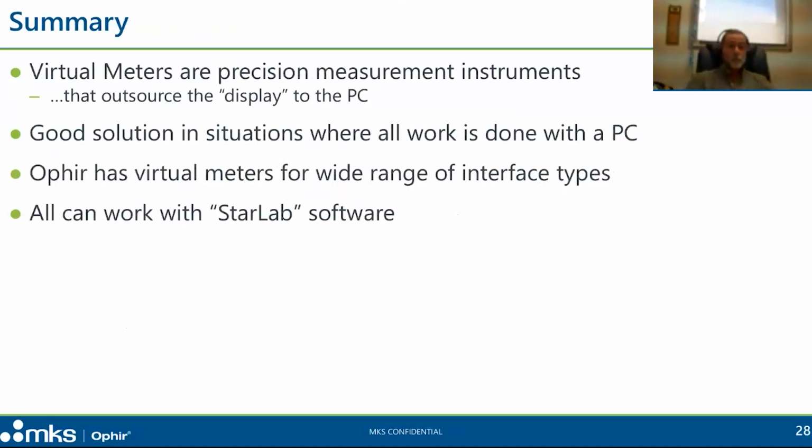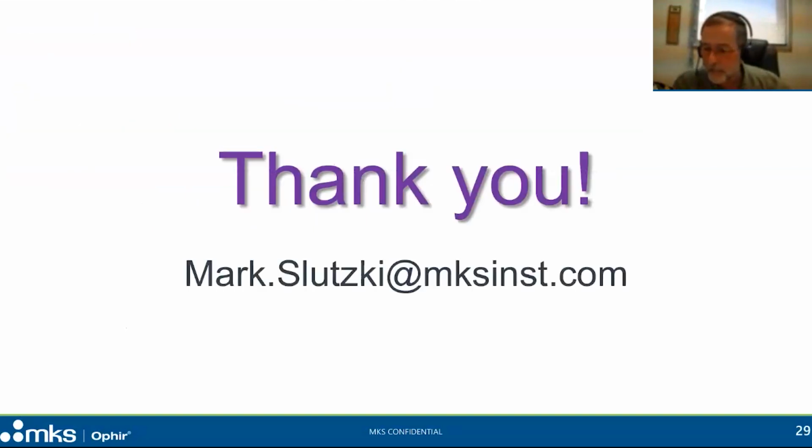So in summary, virtual meters are meters. They're not just interfaces. They're full-blown precision measurement instruments. They also have a recommended annual recalibration, just like the sensors do. They're excellent solutions in situations where all the work is done with the PC and you don't need a handheld meter with its own built-in display. We have virtual meters for a wide range of interface types. All of them can work with our standard StarLab software or with the user's own software. We call that an external system. For you, that would be your internal system. You get the idea. Okay, so that's what I wanted to get across.